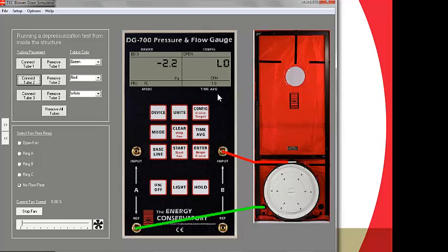Got negative 2.2. And then every 10 seconds, you see it blinked with another one, now negative 2.1. If you're using your app, you could be entering these numbers in now. You need 5 10-second averages. So now we've entered two. Now we're going to enter our third one, negative 2.3. And you'll want to include the sign, too, because on some days, you'll have a wind gust, and you might have a positive number that you need to average in there.